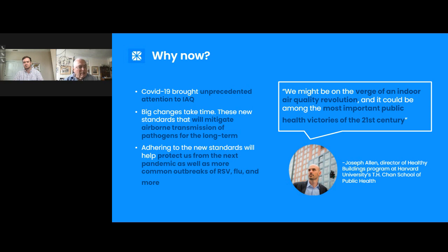For years, CDC documents recommended something like 6 to 12 air changes per hour for isolation and procedure rooms. That was based on how long it would take to clear a contaminated room of something airborne, under static conditions, not ongoing production. So with 6 air changes you could enter fairly quickly, and with 12 even more quickly - it was about clearance of contamination.